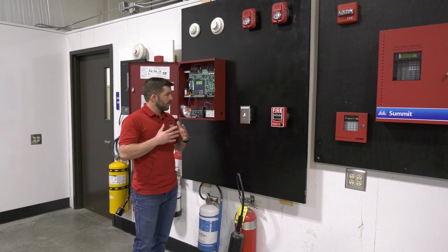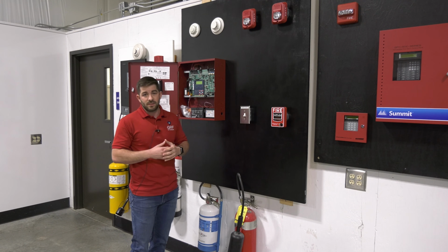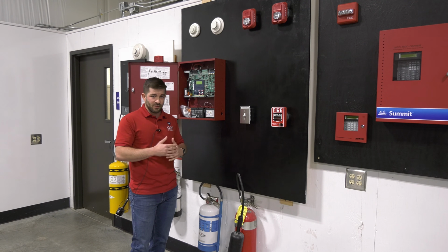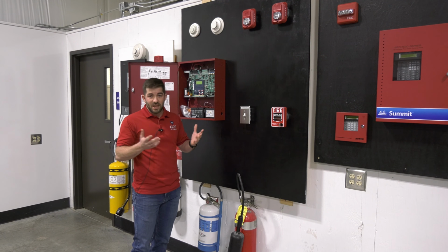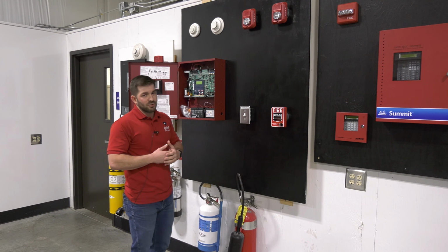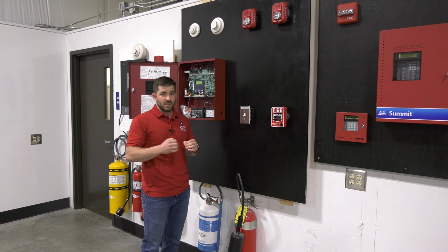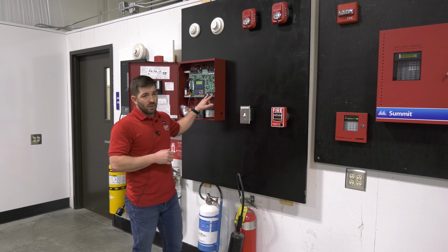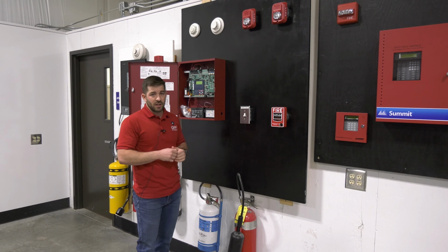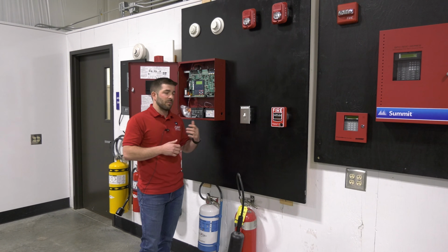Now, 10, 15 years ago, it was all copper lines, onboard DACTs, but now a lot of these phone systems are being transitioned to voice over IP. Voice over IP runs off your internet, and I don't know too many networks that are 100% fail-proof. So most fire alarm panels do not like voice over IP phone lines, because they don't carry that consistent 35 to 50 volts DC that this onboard DACT checks for every 15 to 20 seconds. It does a voltage check. And every time it does a voltage check, if it doesn't see the voltage, you're going to have telco issues. You're going to have communication issues.